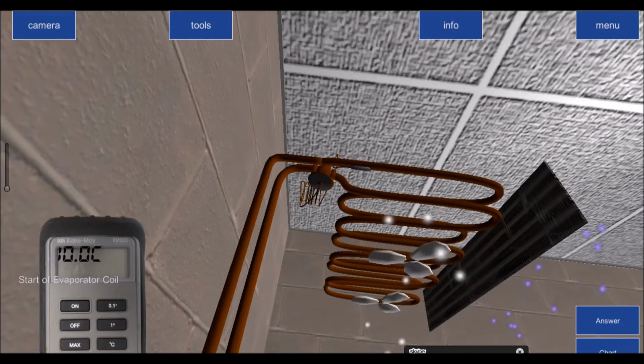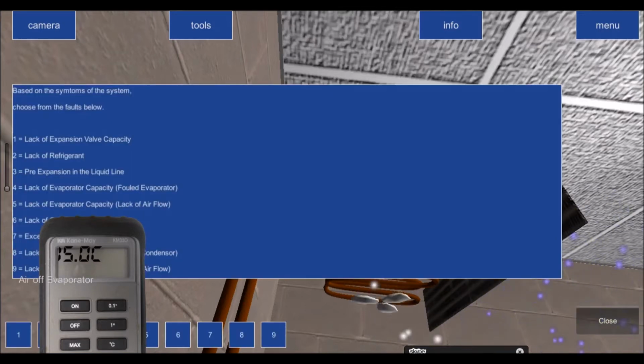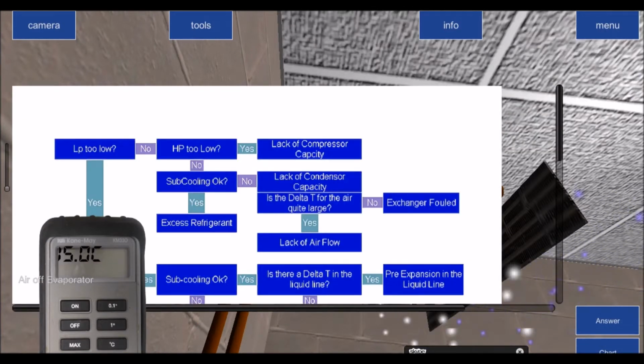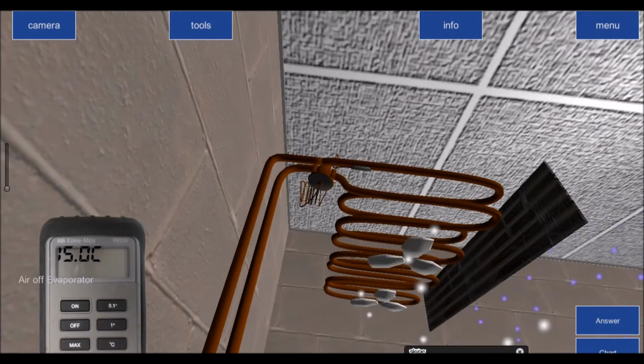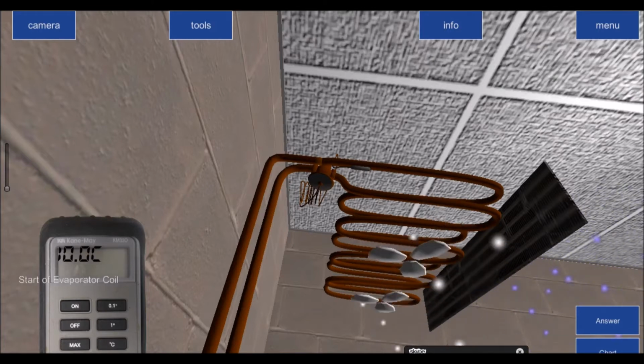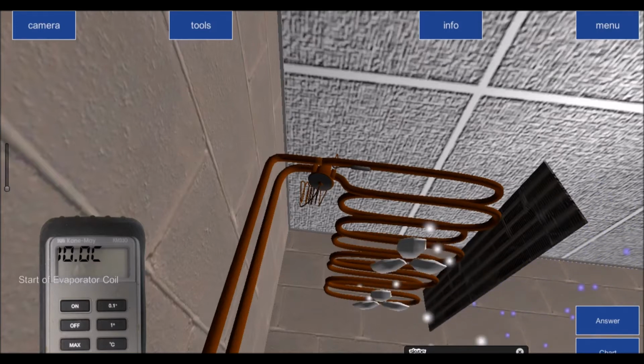So we're able to answer this question, not this one, sorry, this one. Is LP too low? We're able to say no, because we know that for this particular type of system, the delta T total, the difference between the air on temperature and the evaporating temperature, can be anywhere between 5 to 10 degrees of a difference. In this particular case, we have 10 degrees of a difference. It's the maximum amount of difference we're allowed to have, but it's within the range that the evaporator has been designed to operate.